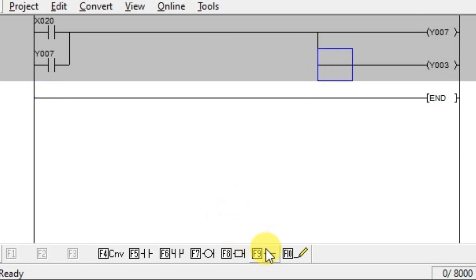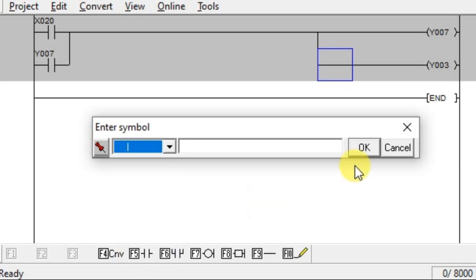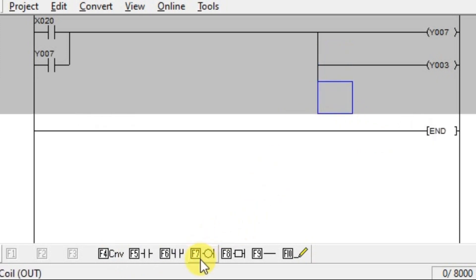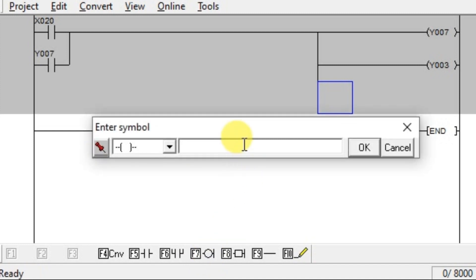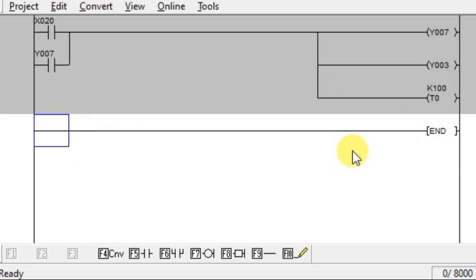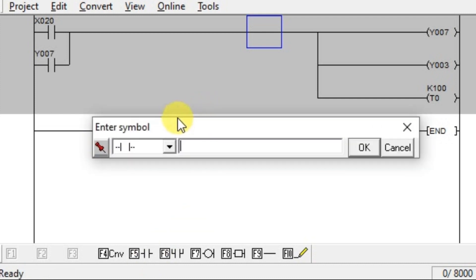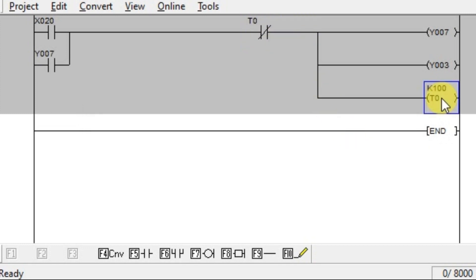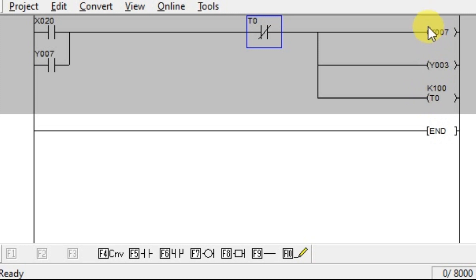Now we have to insert the NC contact of the timer. Take one NC contact and enter timer address T0. The timer is activated after a 10-second delay. Then this NC contact of T0 becomes open, which acts as an unlatching instruction. After 10 seconds, both outputs y7 and y3 will be turned off.